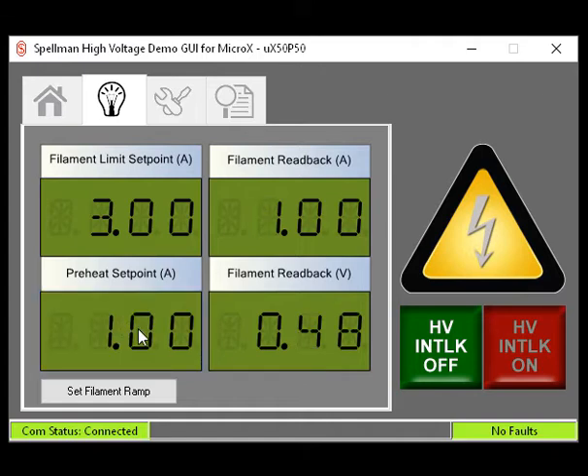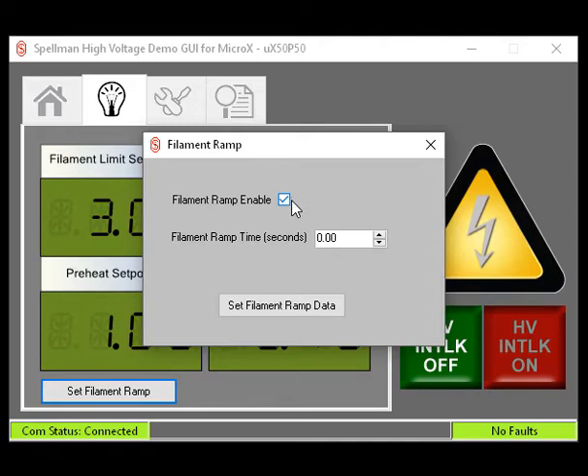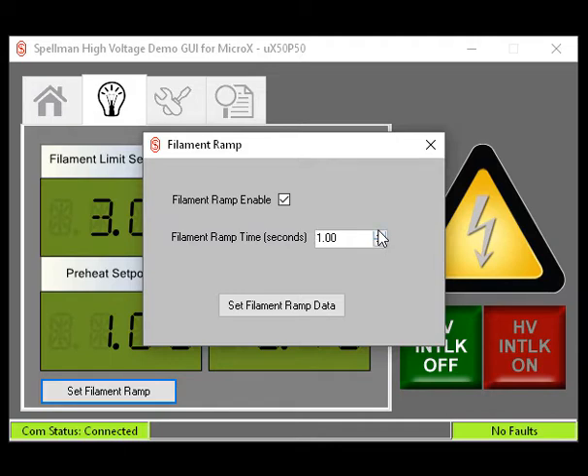Next is the Set Filament Ramp. Click this box. If enabled, the filament will ramp from the preheat setting to the setting required to provide the emission current you desire when the high voltage is enabled. Click the filament ramp enable box. It will allow you to select how many seconds this ramp will take. Click Set Filament Ramp Data and click X to close.